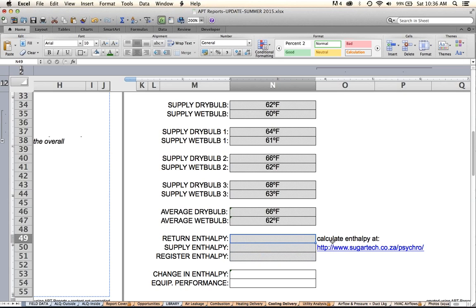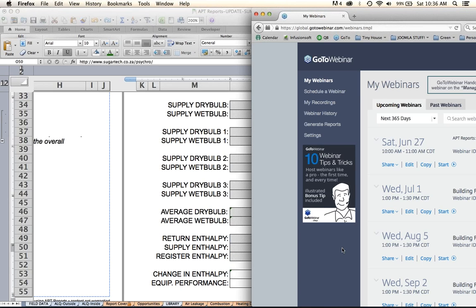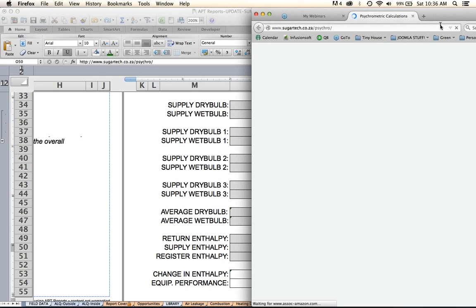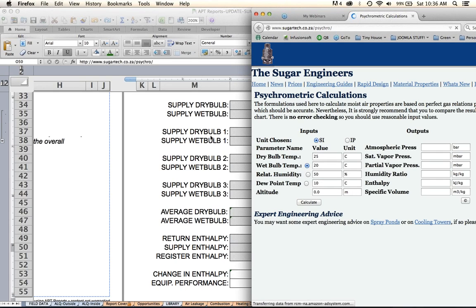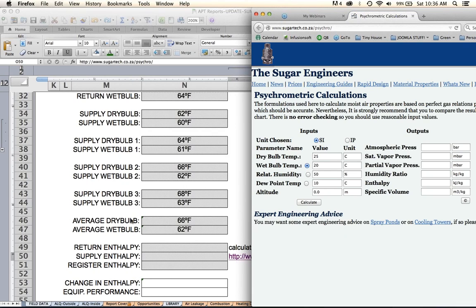to figure out how to get a calculation so we don't have to do this, but we're going to do this anyway. So you're going to have to go to a psychrometric calculator online. So what I'm going to do is enter the average dry bulb, wet bulb, and we're in IP units. This is imperial units. This is standard value. So this is what everybody else in the world uses. This is America, IP. Dry bulb, average 66. Wet bulb, 62.